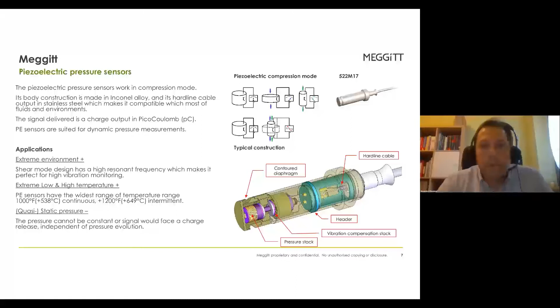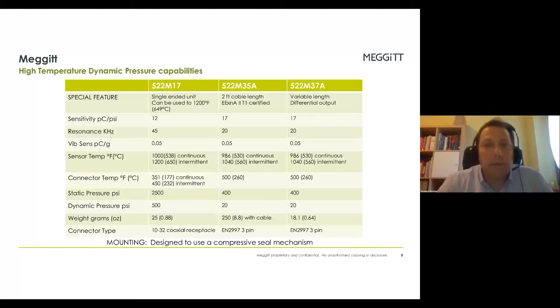Let's go to see our little, exactly. These are the most common units that we design, manufacture, and sell to customers nowadays. The 522 series comes in a number of models and sub-models, but these are the most common in use. Typically for humming and for combustion chamber applications. 538 is the maximum temperature, or 650 in case of intermittent temperature. The sensitivity is 12 or 17 picocoulomb per psi. And we also have the M35A, which is an ATEX version of this pressure unit.